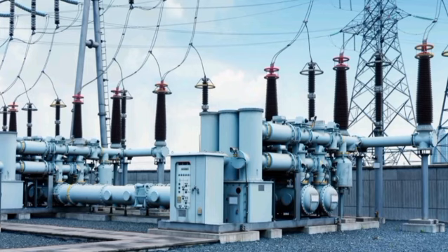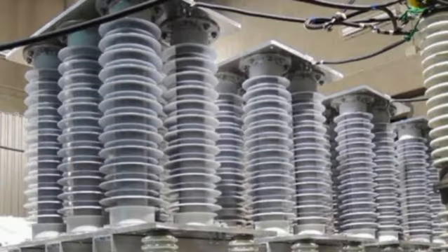Once the surge has ended, the MOV returns to its original high-resistance state, and the surge arrestor resumes normal operation without affecting the power supply. Surge arresters are widely used in residential buildings, industrial plants, substations, communication systems, control panels, solar power systems, and sensitive electronic equipment. They protect against both external lightning surges and internally generated switching surges, ensuring system reliability and extending the service life of electrical equipment.